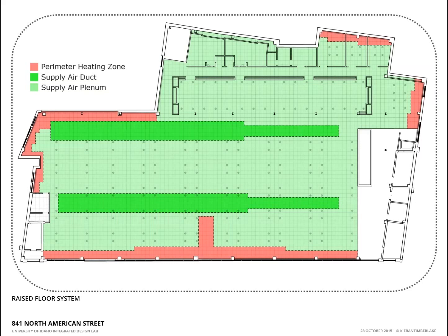So we had a rather novel system deployed at this building, one in which there would be no air conditioning for a building in Philadelphia. I'm not sure how many of you have spent a summer in Philadelphia, but I'll put it rather bluntly, it's hot and humid. And both of those things make for a challenging environment not to have air conditioning. As a mechanism for tempering, we did install an Advantix dehumidification system, which is a lithium salt dehumidification system, a fairly sophisticated one, not typically used in this type of application. You might see it, say, in skating rinks or clean rooms. But it's one in which it's basically as advanced as they get and should be capable of drying out the space very quickly.